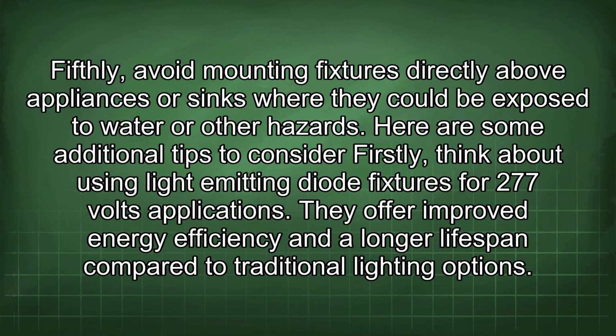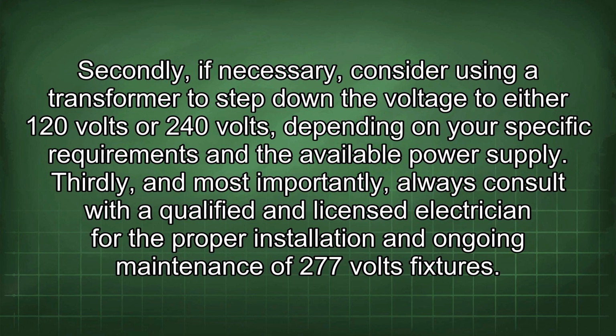Here are some additional tips to consider. Firstly, think about using light-emitting diode fixtures for 277 volts applications. They offer improved energy efficiency and a longer lifespan compared to traditional lighting options. Secondly, if necessary, consider using a transformer to step down the voltage to either 120 volts or 240 volts, depending on your specific requirements and the available power supply.